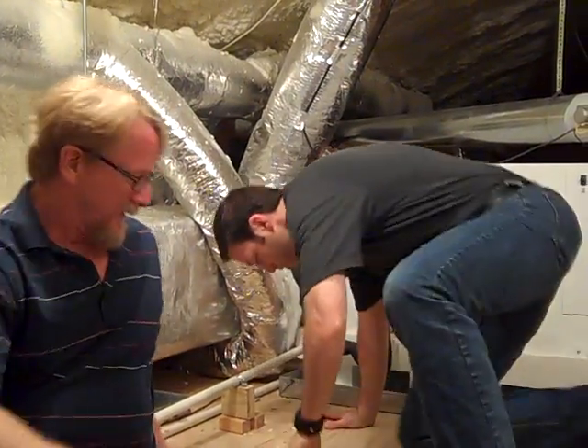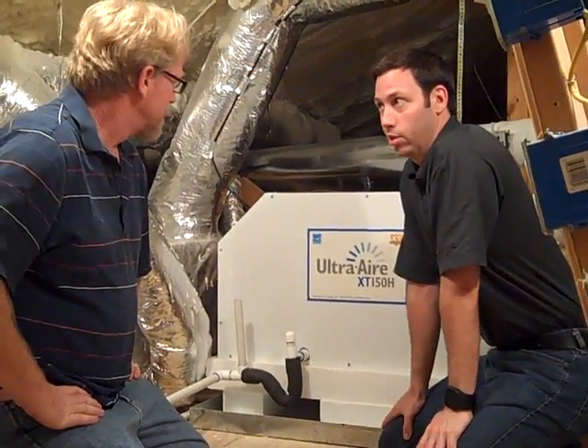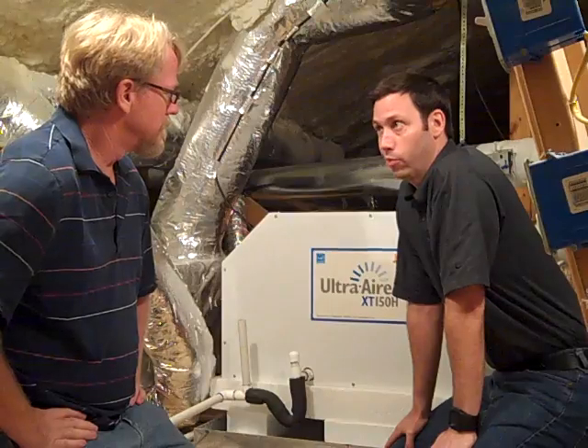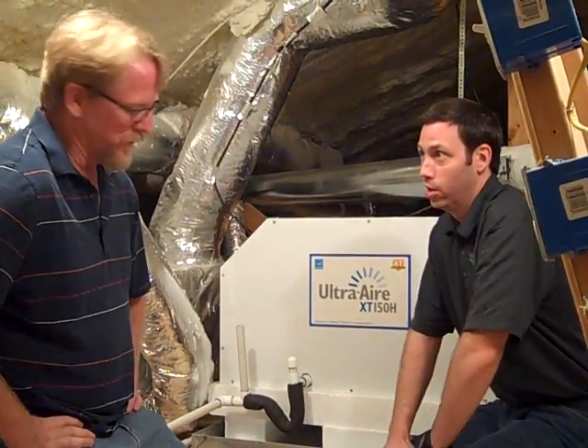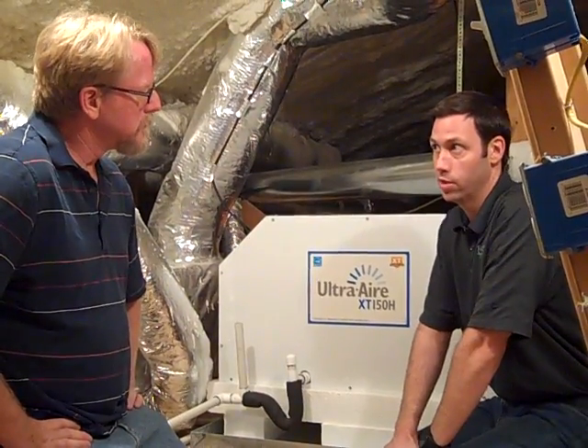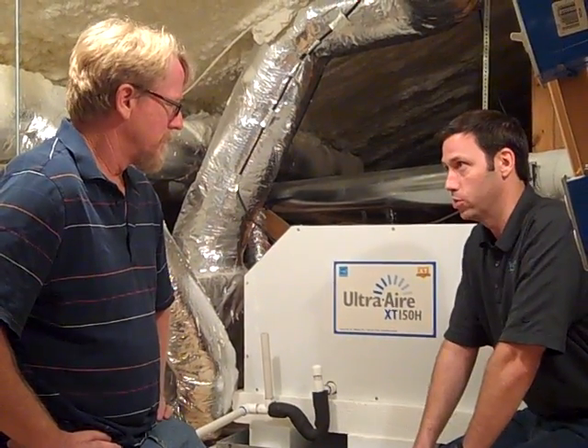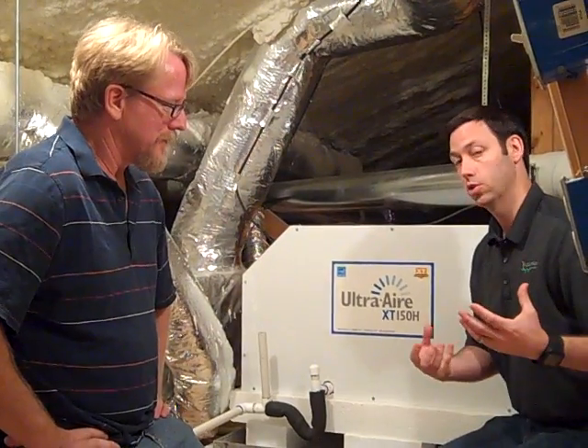Tell us about this big box behind you. This is an Ultra Air 150, and the main purpose of this white box is nothing but dehumidification. These very efficient houses that we're building — this house is at over 900 square feet per cooling ton, which is very good for this climate. There are a lot of times during the season — not necessarily right in the middle of July, but at the beginning or the end of the season — where the temperature may be satisfied in the house and the AC is not running, but it still may be humid inside because it's still humid outside. The sole job of this unit is to bring the humidity down in the house. We actually have a separate humidistat for this unit set at 50% RH, and all this unit does is try to satisfy that RH percentage. So it's a help to the air conditioner in high cooling times, and during the beginning and end of the season it really makes a big difference in comfort.